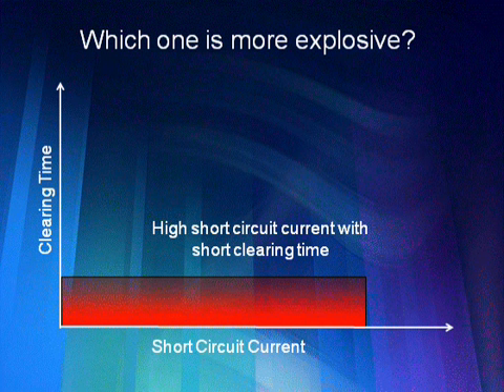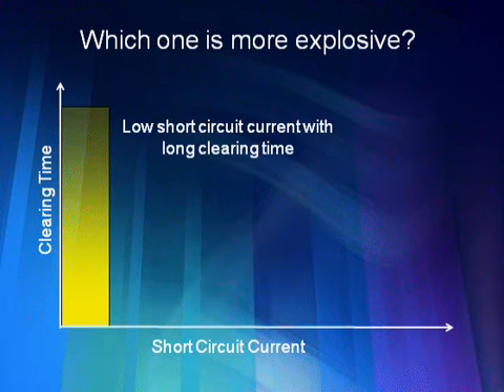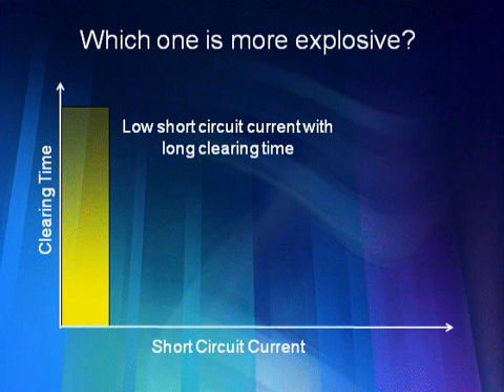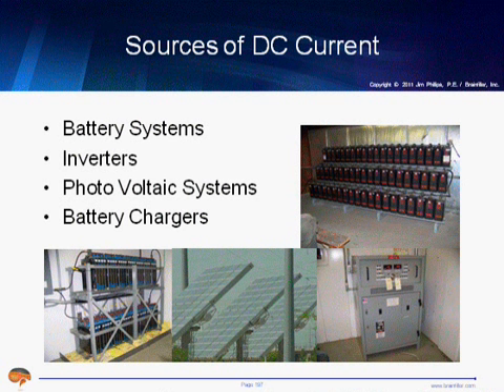But the way the equations are structured, you can also be above 40 calories if you have a very limited amount of short circuit current but a long clearing time. That one most likely is not explosive. So this is another area where good investigation and research is ongoing, and we'll see where this takes us in the future. DC arc flash calculations are going to be the next big thing, and there have been a lot of really good papers presented. Some of them are referenced in the 2012 edition of NFPA 70E, and sources of DC current, they are everywhere.